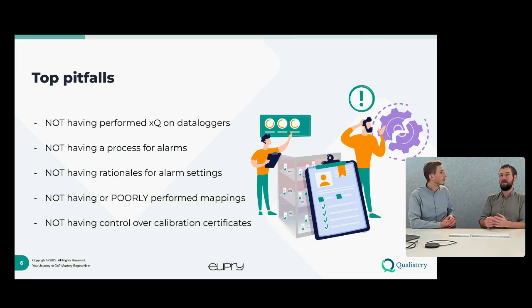Another thing is rationales relating to alarm settings. That's often one of the things that is also greatly discussed at the ISPE forum. How should you set alarm limits? What kind of information leads you to those alarm settings? So in other words, what are your rationales for alarm settings? That's one thing that often is not described well enough. So when auditors come by, the knowledge behind why those alarm settings were chosen is not readily available.